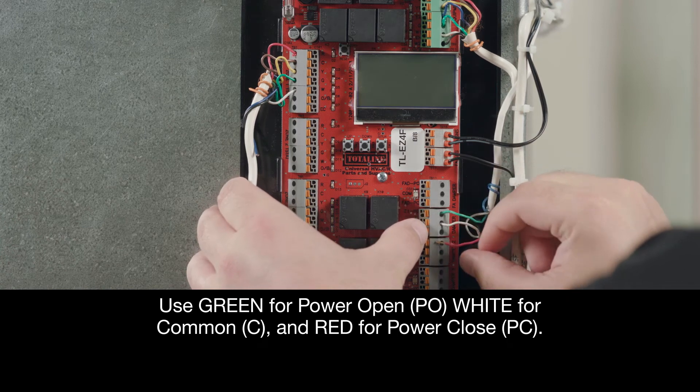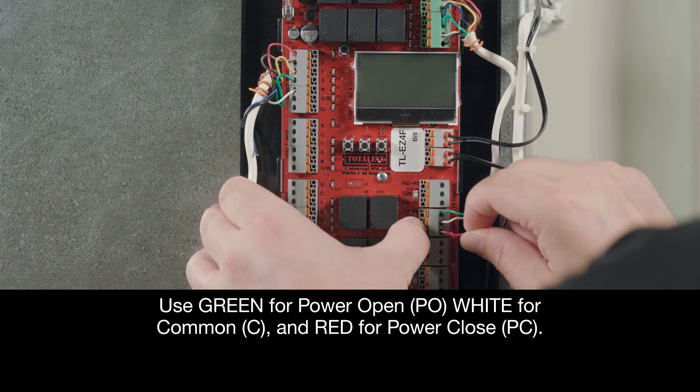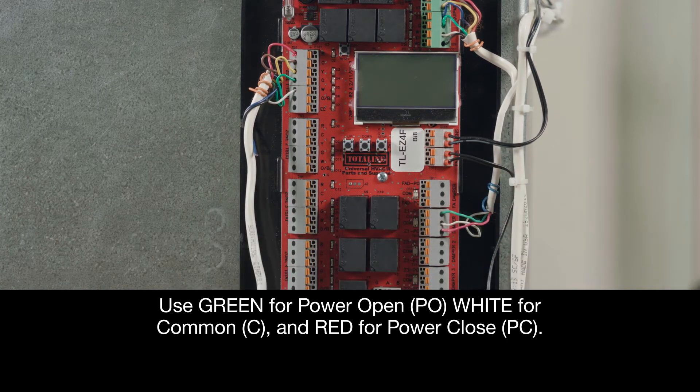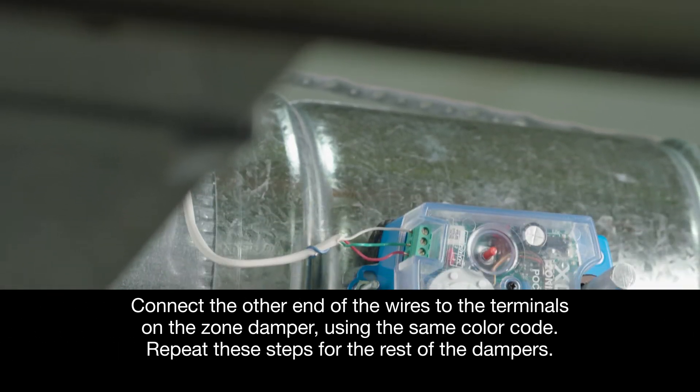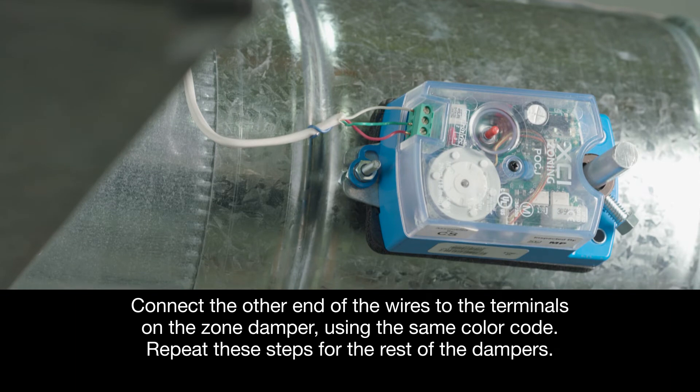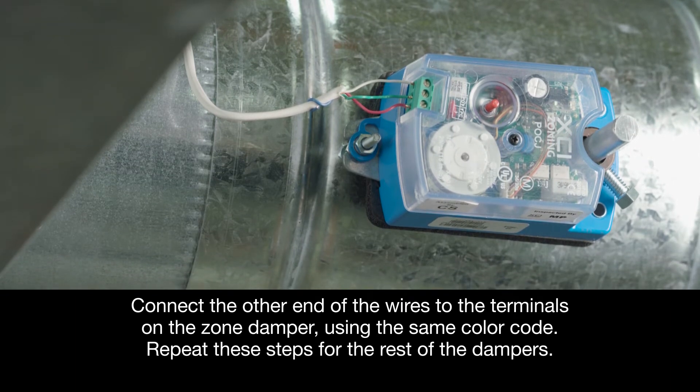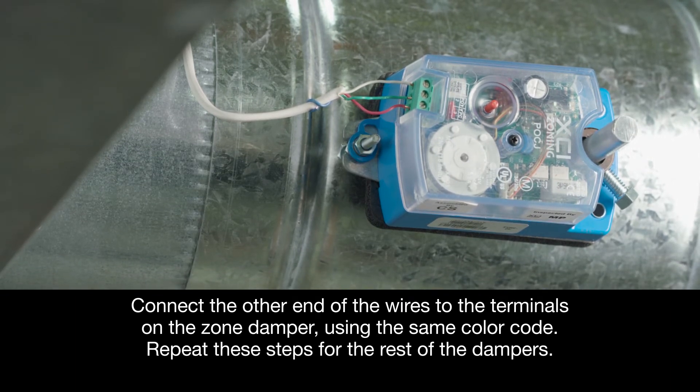Use green for power open, or PO, white for common, or C, and red for power close, PC. Connect the other end of the wires to the terminals on the zone damper using the same color code. Then, repeat these steps for the rest of the dampers.